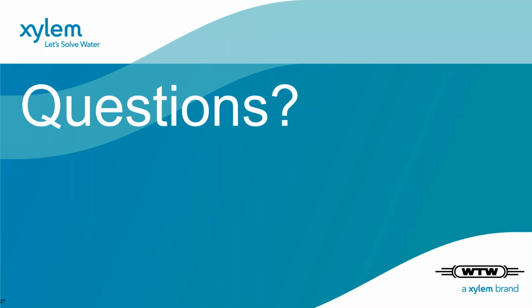Okay, thank you. What is the maximum possible distance between the sampling point and the analyzer? We provide tubing for up to 25 meters. And one additional comment: the maximum height of pumping is 5 meters. For that 5 meters, an additional check valve has to be added so that you avoid the sample running back instead of being pumped.